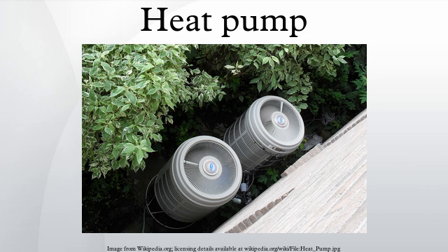In residential and commercial applications, the hydrochlorofluorocarbon R22 is still widely used. However, HFC R410A does not deplete the ozone layer and is being used more frequently. Hydrogen, helium, nitrogen, or plain air is used in the Stirling cycle, providing the maximum number of options in environmentally friendly gases. More recent refrigerators use R600a, which is isobutane, and does not deplete the ozone and is friendly to the environment. Dimethyl ether is also gaining popularity as a refrigerant.